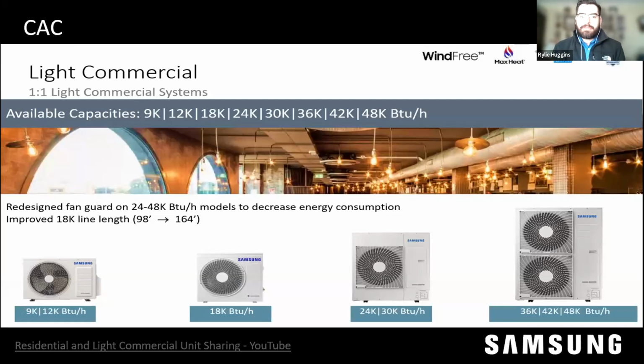Now I'm going to get into the CAC. Like I said, the CAC is more based on the capability of the outdoor unit, which came out with our new generation this year. We changed a lot of things in the design to help decrease energy consumption but also improve longer line lengths and give you better capabilities on commercial jobs. For example, our 18K, the second one from the left, was 98 feet total line length, and now it's 164 feet. We really increased the capability of the unit.